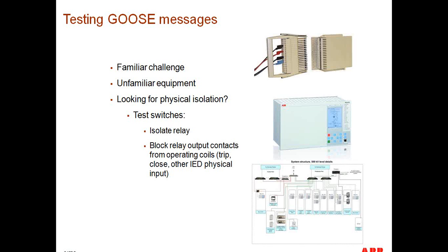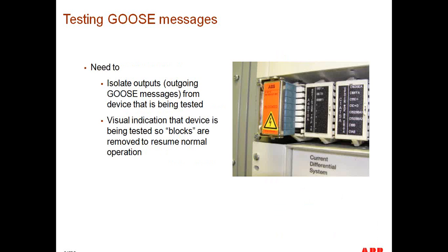So today, with hardwired connections, we use test switches to isolate the relay, to block relay outputs from operating coils, whether they are trip coils, close coils, or physical inputs from other devices. So how is that done? One of the key requirements is that the testing of GOOSE messages needs to replicate the behavior of testing with hardwired equipment. Outputs need to be isolated. In our particular case, this means that the outgoing GOOSE messages from devices that are being tested need to be blocked, need to be supervised somehow. Somehow we need to tell the system that those messages need to be blocked. But at the same time, those messages should allow for devices to perform the testing.